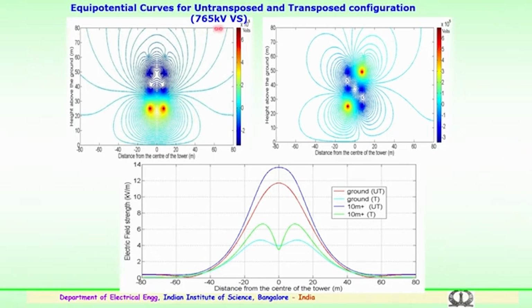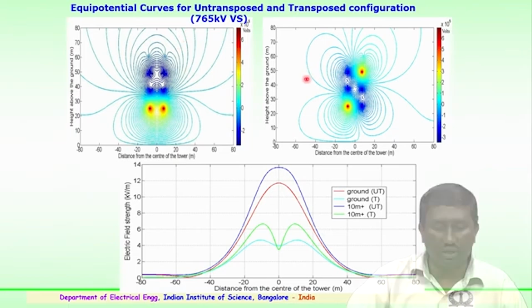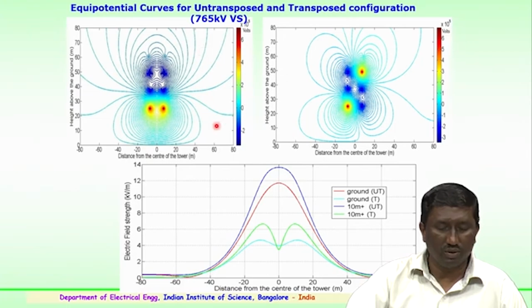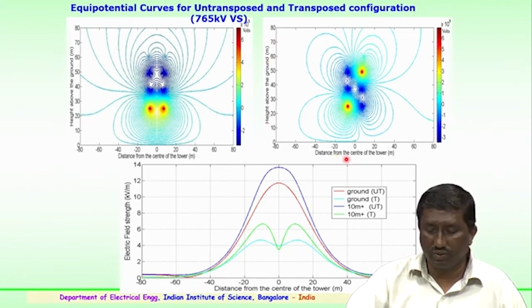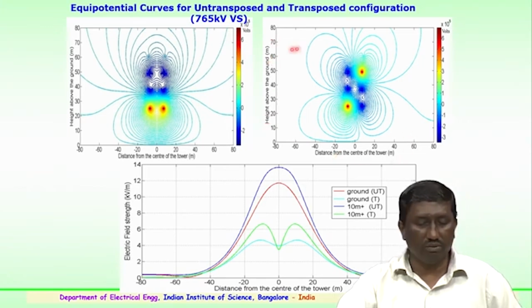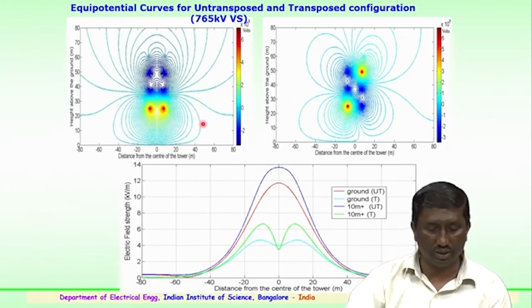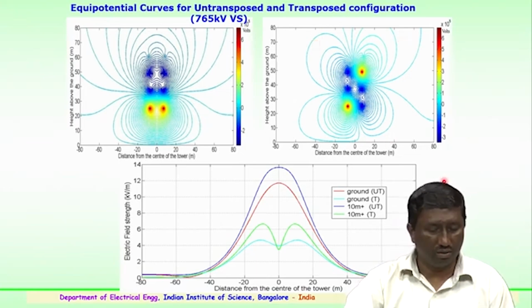So, for a 765 kV line the curves have been shown both for the untransposed normal tower 765, and for the transposed tower. You can see height above the ground versus the distance from the center of the tower. These are the equipotential plots which give an indication, and this gives the electric field strength from the center of the tower.